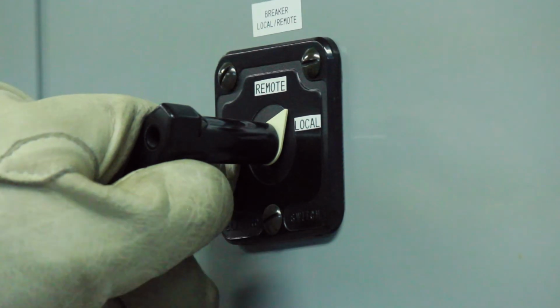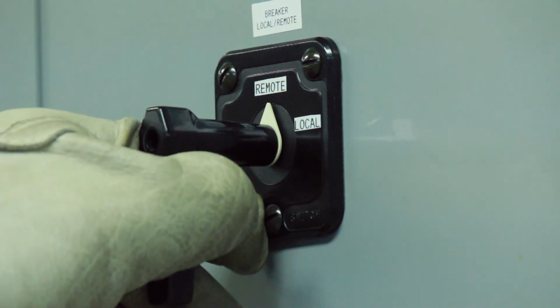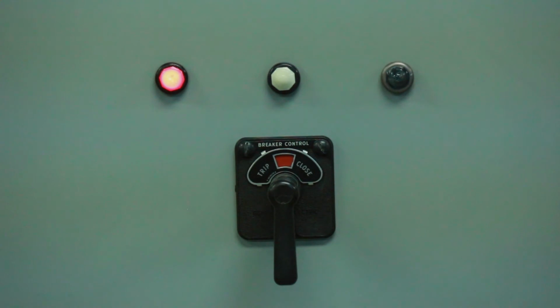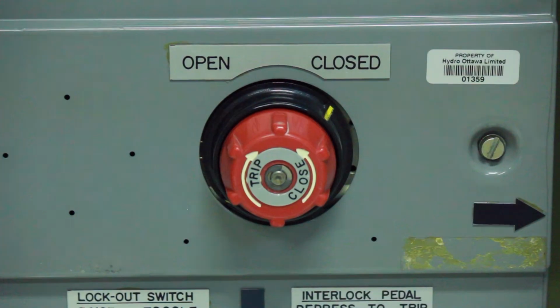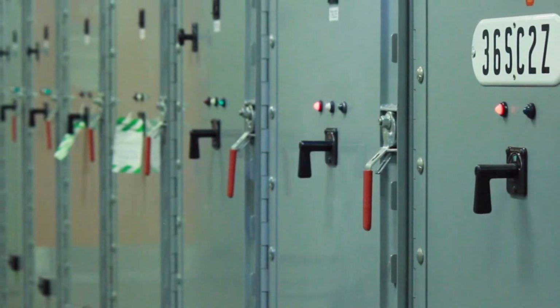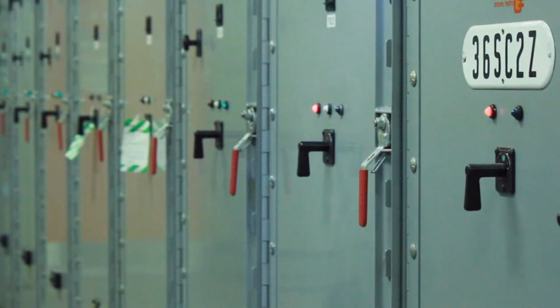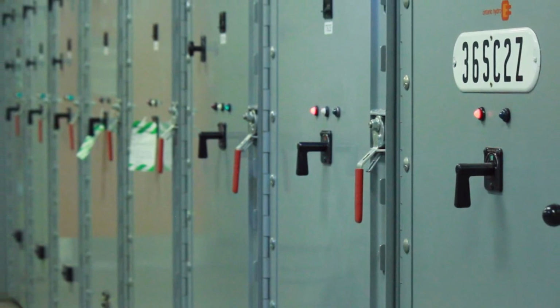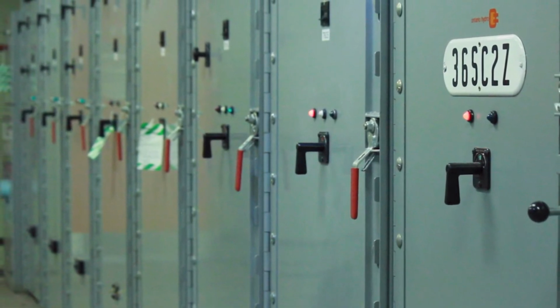At the breaker panel, switch the controls from local to remote. Call System Office to remotely close the circuit breaker. The breaker indicator light will switch from red to green, indicating the breaker is now closed. If there are any further questions regarding how to operate the equipment, contact System Office or your immediate supervisor.